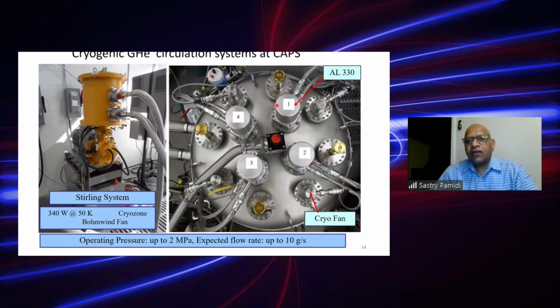So to talk about helium circulation systems, we have several. This is the system we use for the cable demonstration we showed before, and we also have larger helium circulation systems. As I said, one of the challenges in helium gas cooled superconducting devices is the circulation system itself. So we have built a system where we have 4 cryocoolers, and each one has its own heat exchanger and also its own circulation fan. Basically, even though it's one system, it is 4 circulation systems working in parallel.